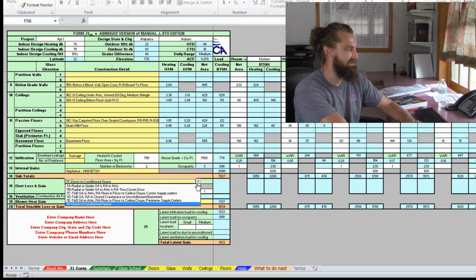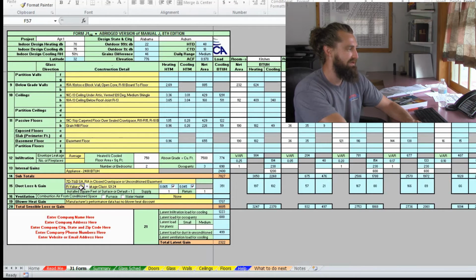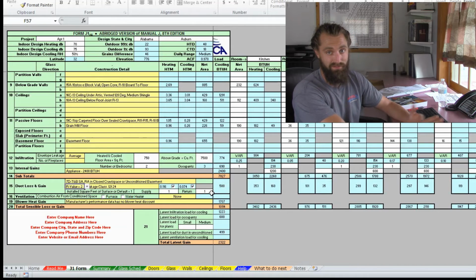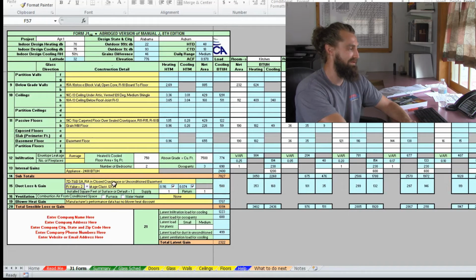If they weren't in conditioned areas, say an unconditioned crawl space with R2 insulation, or if it were sheet metal with no insulation, though they don't even give you that option here, you could see what your BTU heat losses and gains are through the ductwork. Then there are leakage classes, so let's say we had super leaky ductwork, you'd see how much BTU movement or loss you're getting through that. We have to account for all that if it's unsealed ductwork. And if we had super tight ductwork, you'd see where we're at there too.